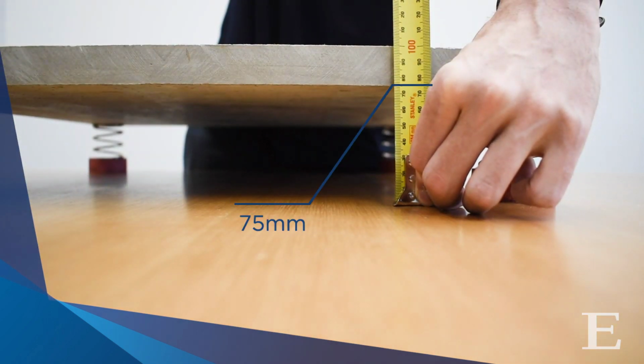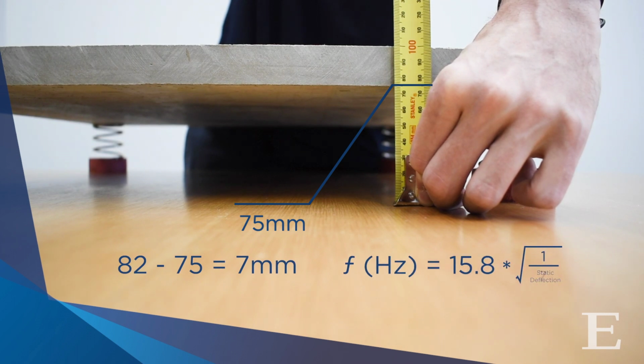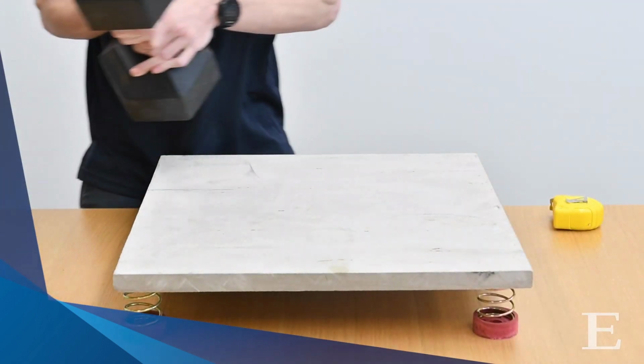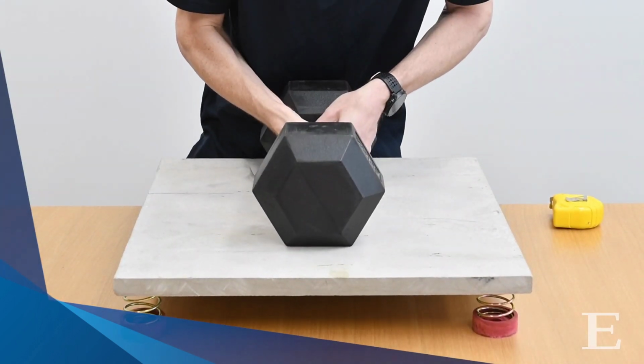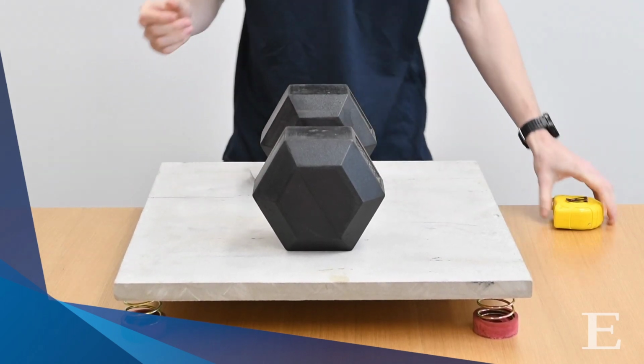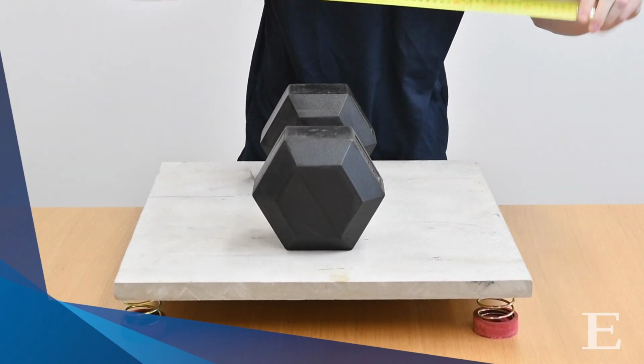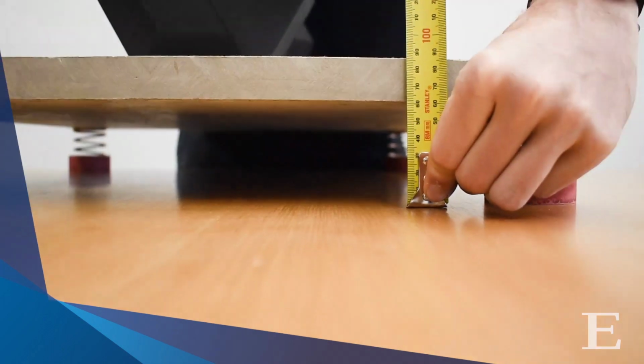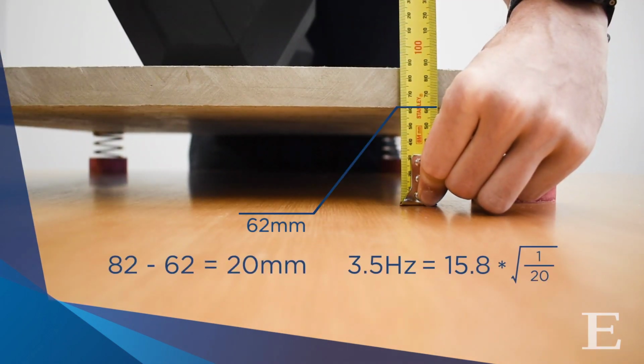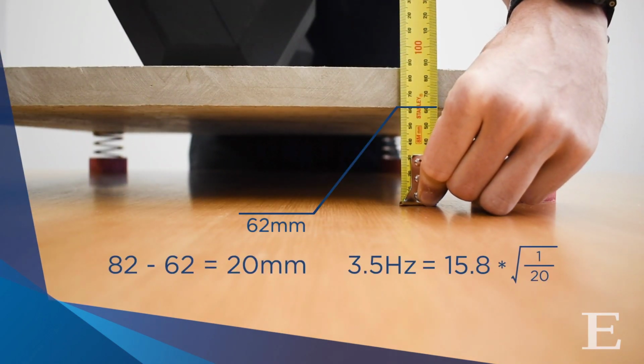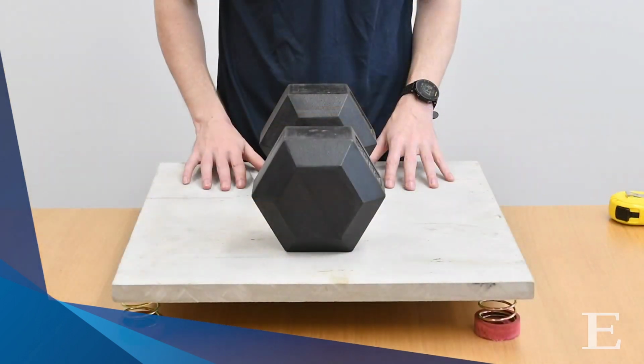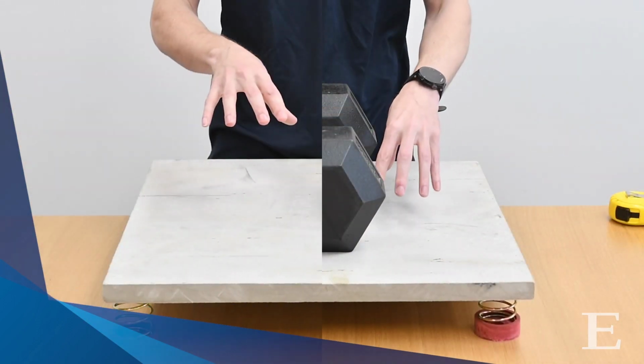So that tells me that I've got 7mm of static deflection. I can put that into my natural frequency equation, and that tells me that my natural frequency is 6 Hz. If I add more mass, 25 kilograms, I can see that my platform was visibly deflected further. Retaking my static deflection measurement, I'm now getting about 20mm, which is 3.5 Hz when we plug it into our natural frequency equation. Side by side, I give this an excitation.